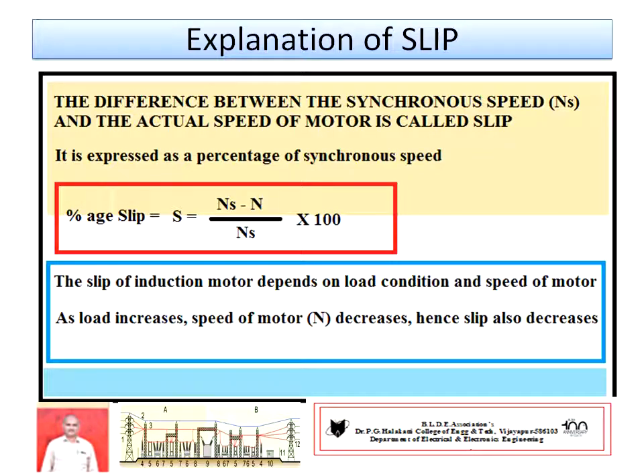Slip is defined as the difference between synchronous speed Ns and actual speed of the motor N. It is expressed as a percentage of synchronous speed: percentage slip s = (Ns − N) / Ns × 100, where N is the rotor speed or actual speed of the motor, and Ns is the synchronous speed, given by Ns = 120f / P, where f is the supply frequency and P is the number of poles. Slip is denoted by s.